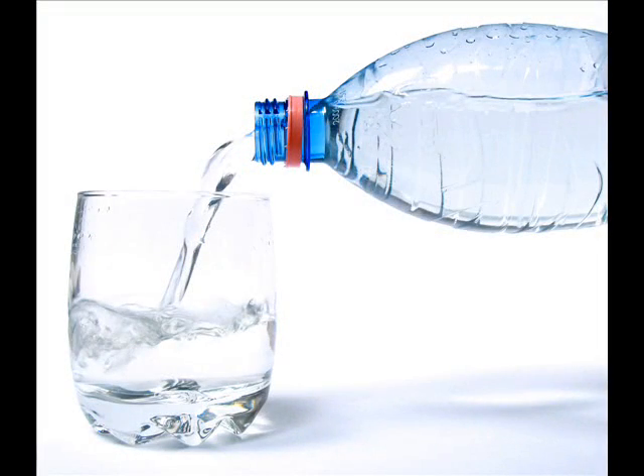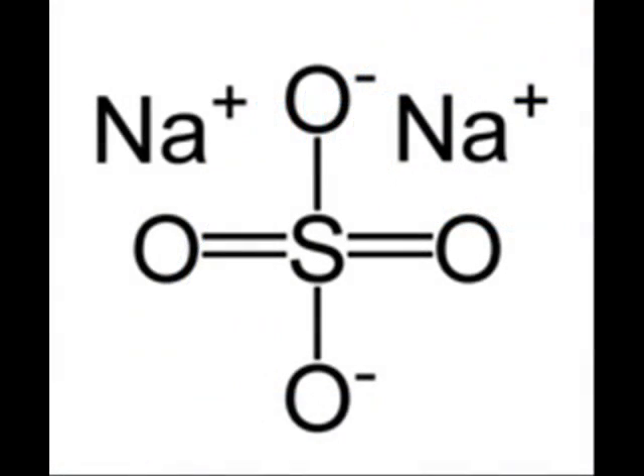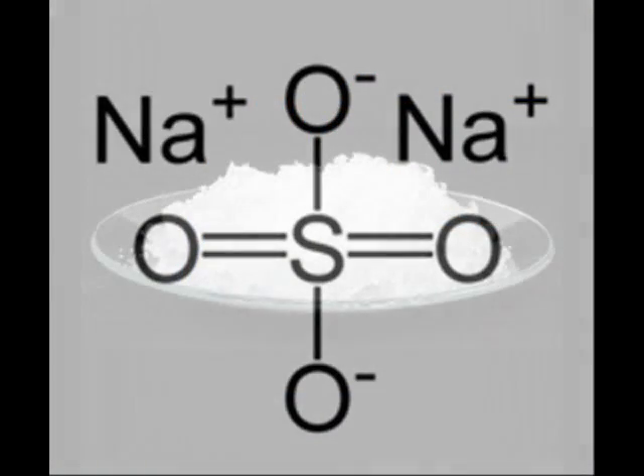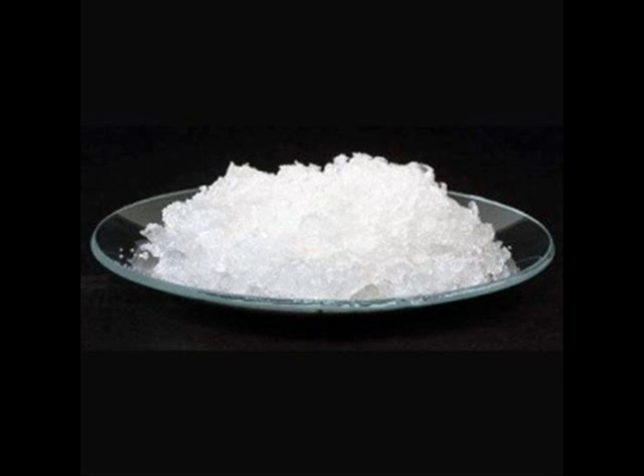What's so special about water? Heat can be stored in many materials. For example, eutectic salts like sodium sulfate decahydrate, commonly known as Glauber salts, give off about 50 BTUs of heat per pound when changing from liquid to solid at 90 degrees Fahrenheit. They take up less space than water for the amount of heat they store. So what's wrong with eutectic salts?